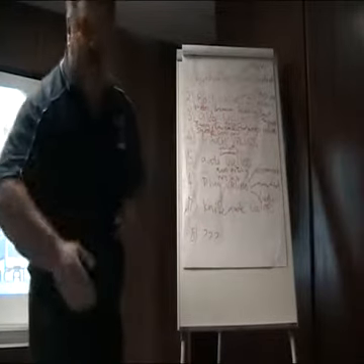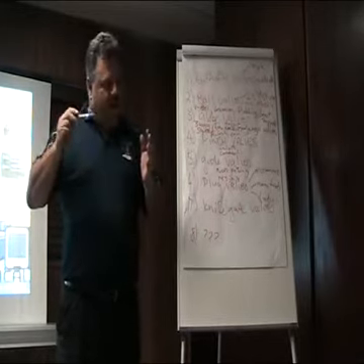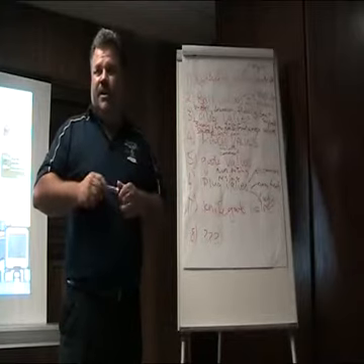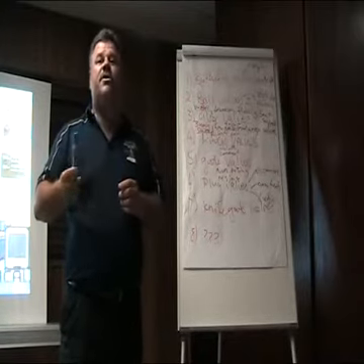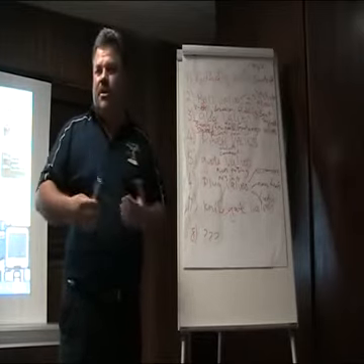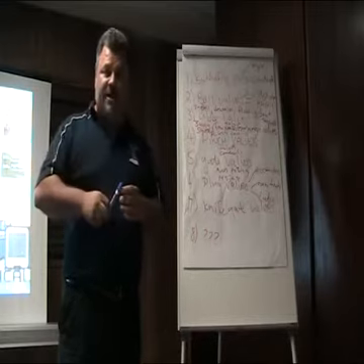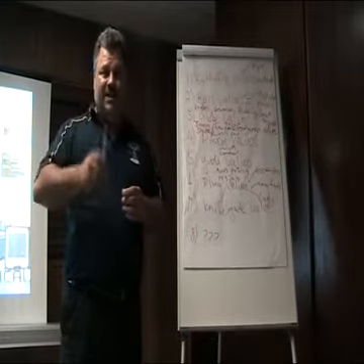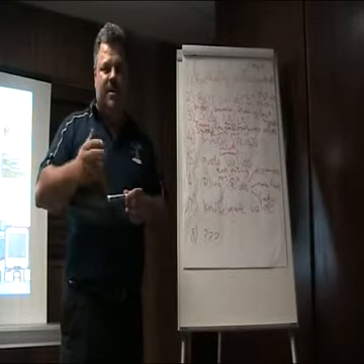So when you close this thing, you don't want a class 6, nor a class 4, not a class 5 metal. You want no leak through there. There are no such specs in South Africa because the specs were written years ago when the technology was not available. These days the technology is available. When you say you want an isolation valve, there are valves on the market to do isolation properly. Zero leakage. Okay, I just wanted to bounce that off.